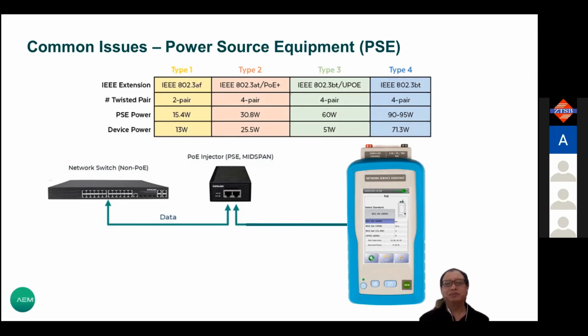It's a very simple measurement - you just plug in and measure. If it's not giving you the right wattage, or too low power, either you need to change the equipment or change the cable. If the cable has no issue and the DCR meets the TIA standard, you need to change the equipment. This gives you assurance on what the output of your PoE is.